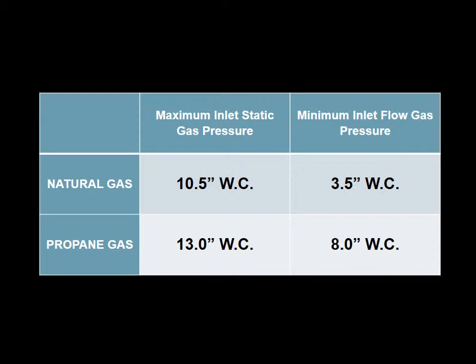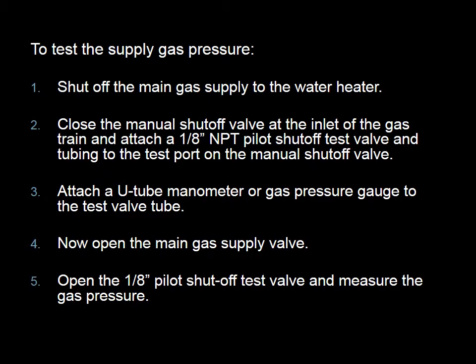For natural gas, the maximum inlet static pressure must not exceed 10.5 inches water column and must not drop below 3.5 inches water column during operation. For propane gas, the maximum inlet static pressure must not exceed 13 inches water column and must not drop below 8 inches water column during operation.